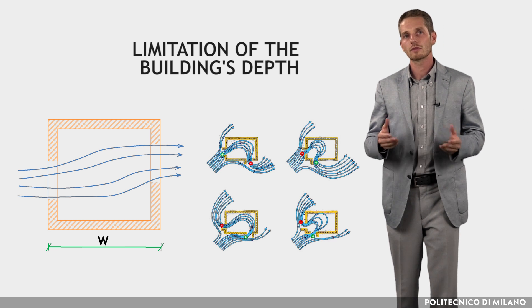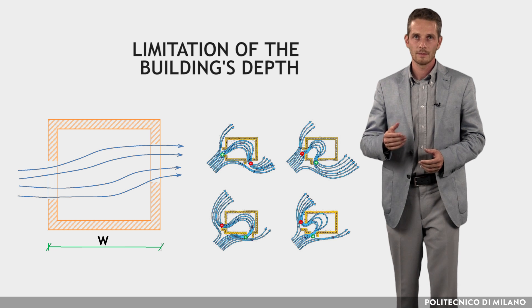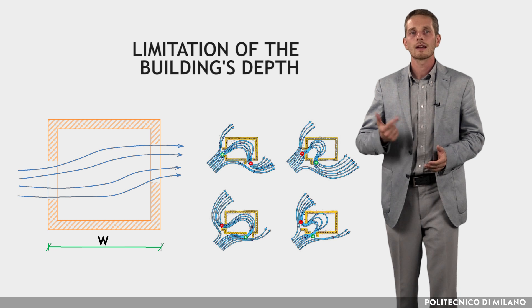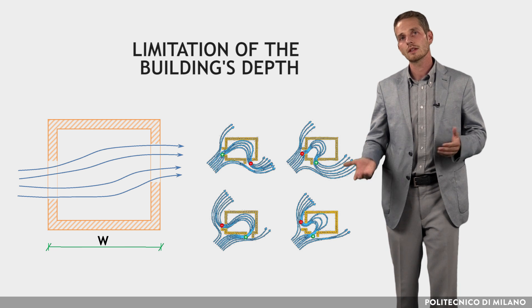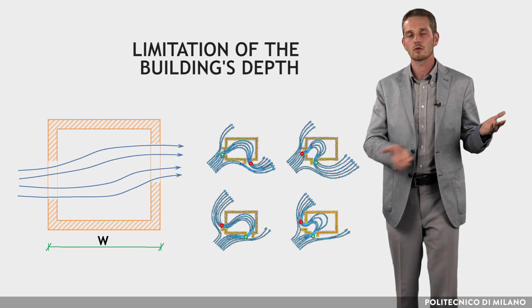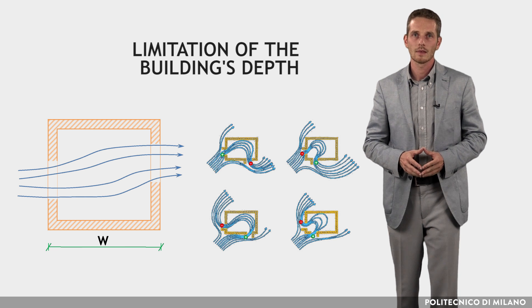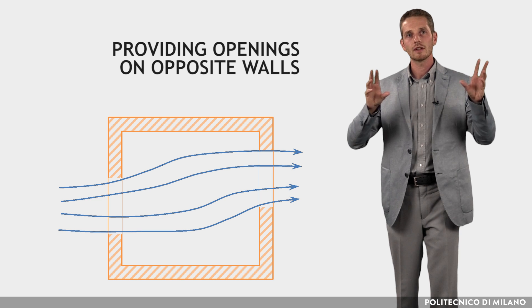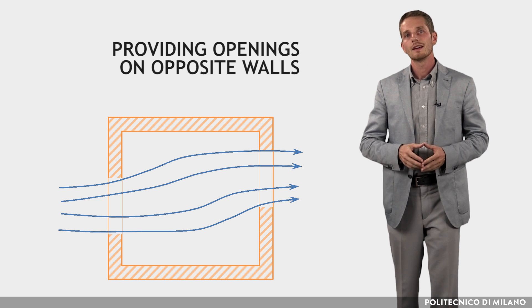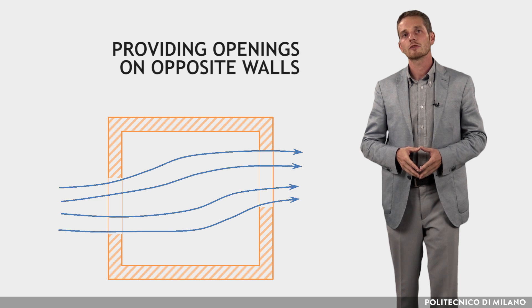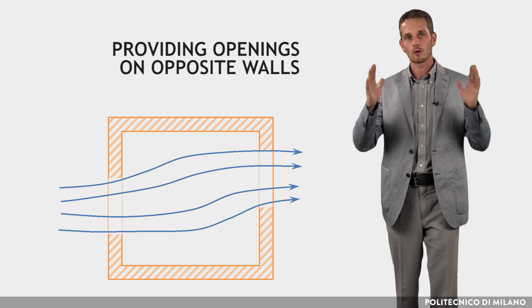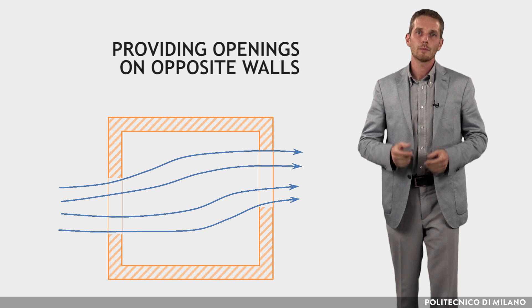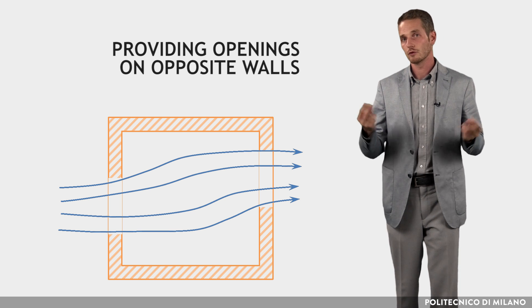Architectural elements can be used to harness prevailing winds. Architectural features like wind walls and parapets can be used to create positive and negative pressure areas to induce cross ventilation. Since airspeed inside a space varies significantly depending on the location of openings, the most effective strategy is to provide staggered openings on opposite walls. Room width should be limited if openings cannot be provided in two walls.